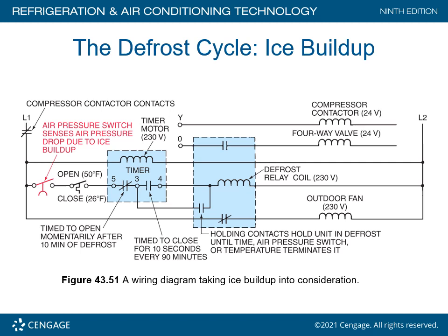Okay, in this timer here, it's timed to close for 10 seconds every 90 minutes. So what happens is every 90 minutes, these contacts will close for 10 seconds. Now, these other devices are not closed, so we're not going to go into defrost. It's as simple as that.